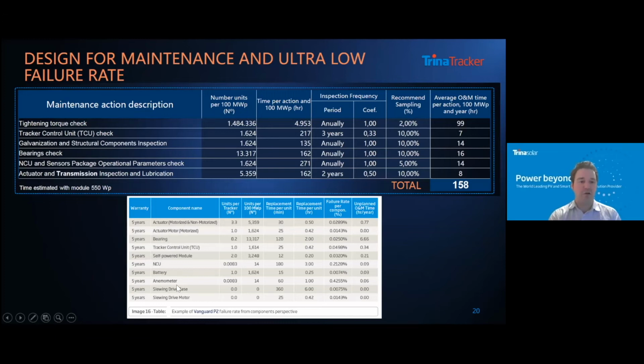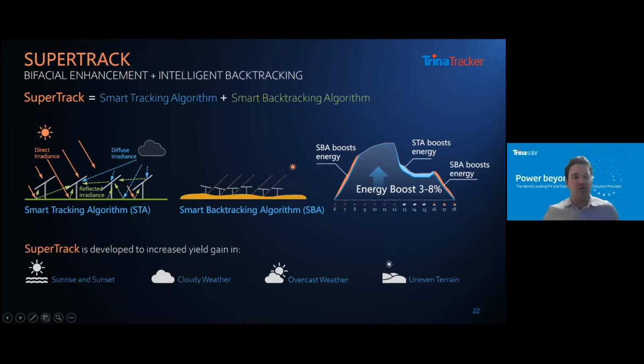And you can see here on the corrective maintenance, the failure rate of all of the key components here, the actuators, the drives, the bearings, they're all way less than 1%, 0.02, 0.04%. So very, very low O&M risk with a well-proven bankable tracker like Trina. We also utilize intelligent tracking to further boost the energy when you use bifacial modules on our tracker.